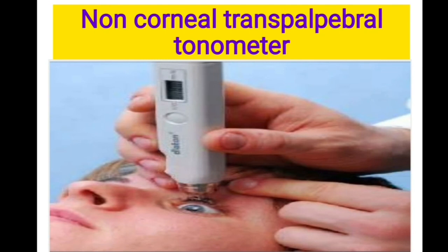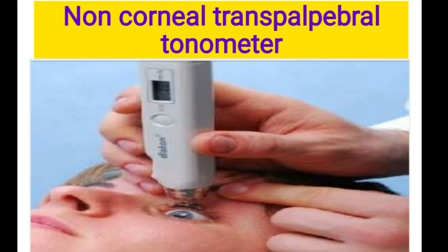Pneumotonometer is also based on the principle of applanation tonometry. It measures IOP by flattening the cornea with a graded flow of gas against a flexible diaphragm. Very useful in scarred corneas, edematous corneas, and over soft contact lenses. The non-corneal transpalpebral tonometer measures IOP through the eyelids overlying the sclera; a free-falling rod rebounds against the tarsal plate to give the IOP measurement, with no risk of corneal damage. The ocular response analyzer (ORA) is an adaptation of the NCT — it uses an air puff but corrects for the effects of corneal hysteresis on IOP measurement, giving better readings compared to standard NCT.